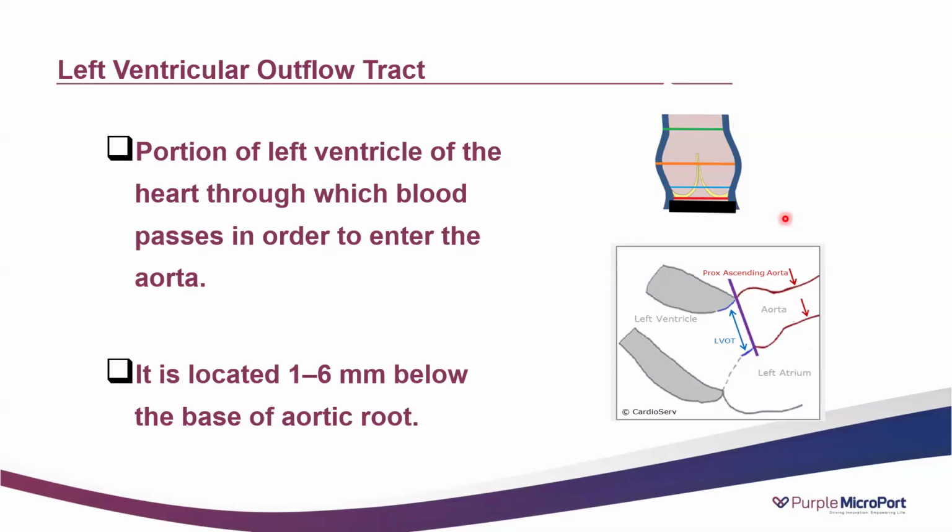Just in the interest of the audience, please don't get confused. This is the landing zone. You have to keep it 3 to 4 mm deep to avoid any kind of pacemaker implantation.